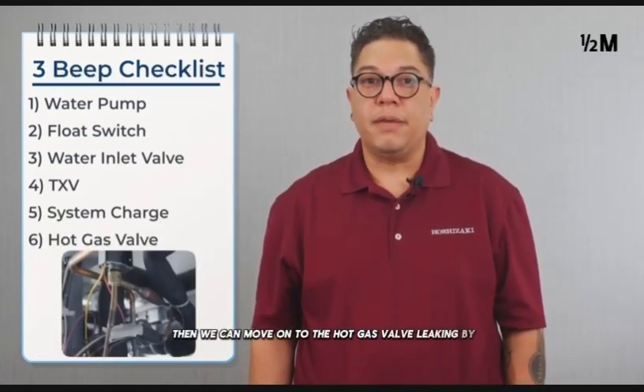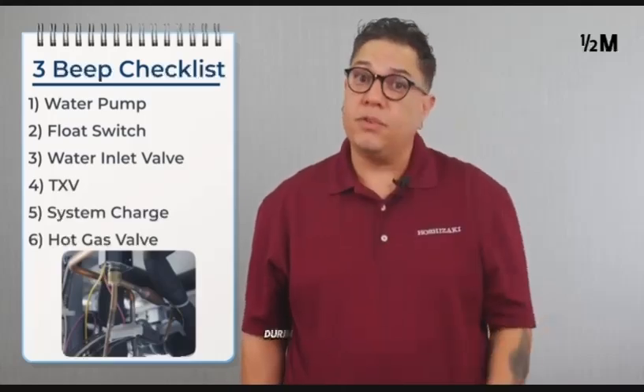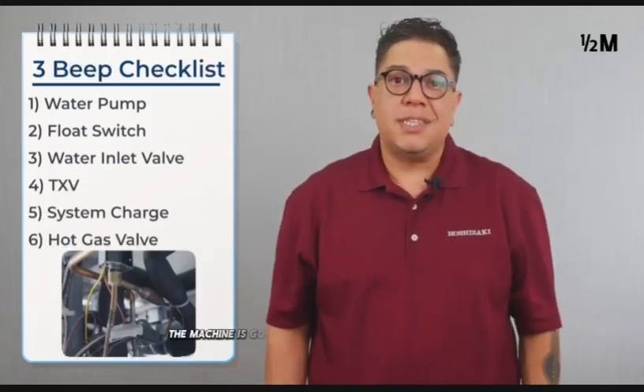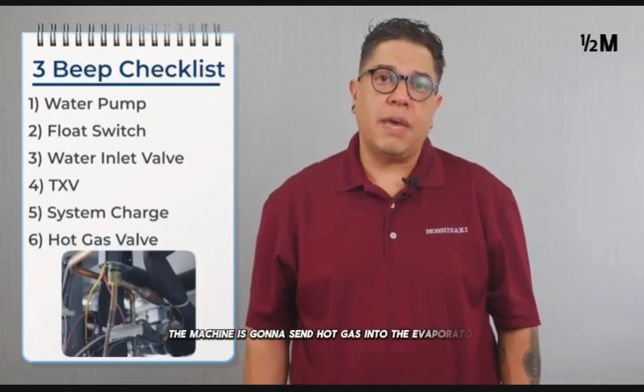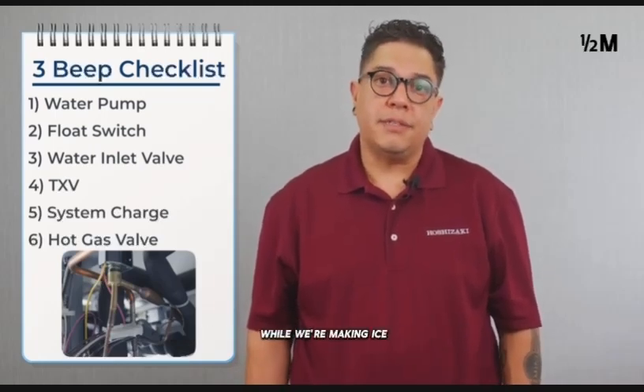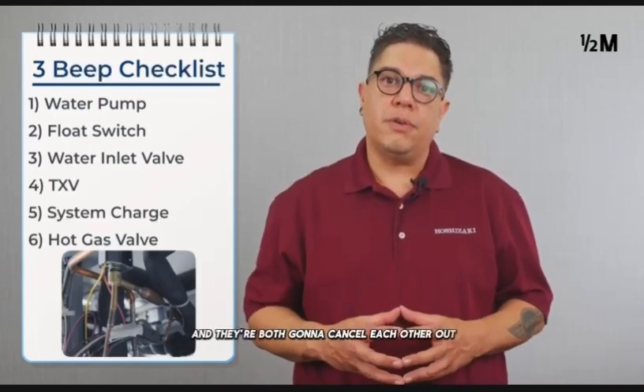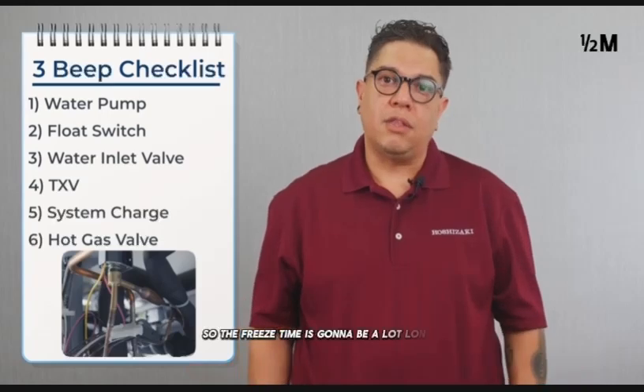Once we confirm that the charge is correct and accurate, then we can move on to the hot gas valve leaking by. If the hot gas valve is leaking by during the freeze cycle, the machine is going to send hot gas into the evaporator while we're making ice. And they're both going to cancel each other out. So the freeze time is going to be a lot longer.